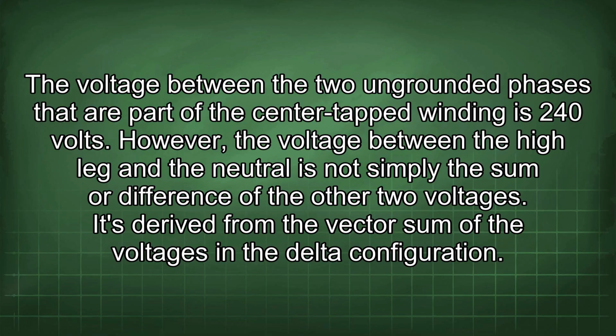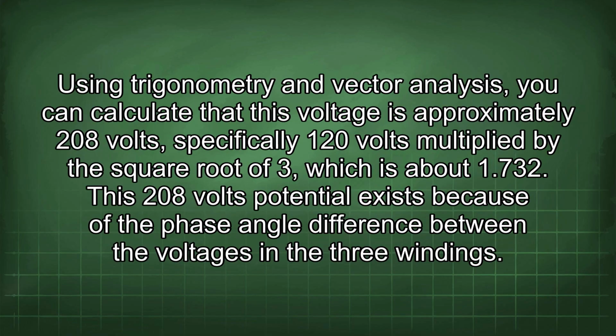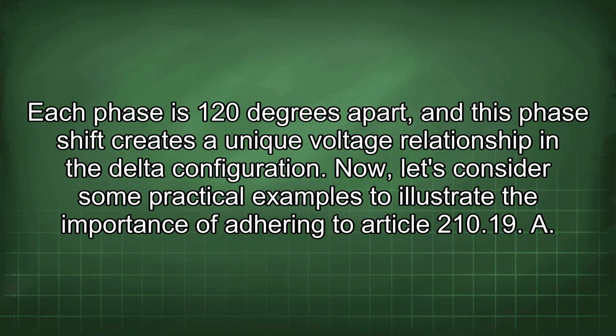However, the voltage between the high leg and the neutral is not simply the sum or difference of the other two voltages. It's derived from the vector sum of the voltages in the delta configuration. Using trigonometry and vector analysis, you can calculate that this voltage is approximately 208 volts, specifically 120 volts multiplied by the square root of 3, which is about 1.732. This 208 volts potential exists because of the phase angle difference between the voltages in the three windings. Each phase is 120 degrees apart, and this phase shift creates a unique voltage relationship in the delta configuration.